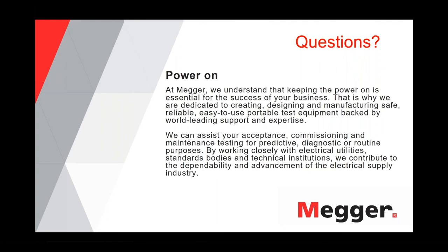Now, if you would change such a cable, and that happens quite often, people replacing paper sections with XLP, that obviously changes the whole leakage current for the feeder. So you have to reestablish the leakage current number for that particular feeder after you do a major cable exchange. Okay, but it's a straightforward solution. You need some experience, and the experience comes from the historic data you have on these cables.